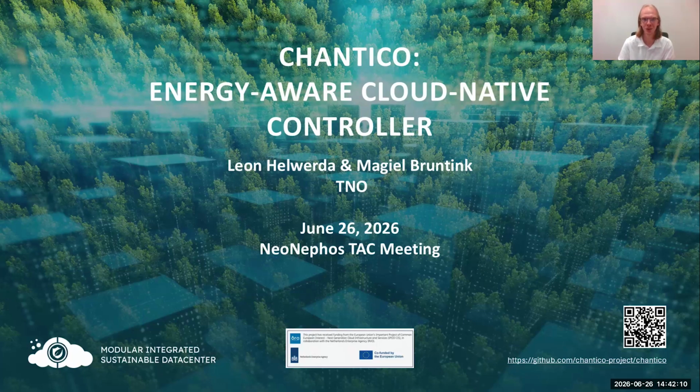We have noticed that it is slower to obtain these measurements via IPMI, and there is a larger window that you obtain for these metrics. We really want to obtain our data in the highest resolution possible. That's also why we have looked into monitoring from bare metals directly, because sometimes some PDUs do not provide the resolution that we need.